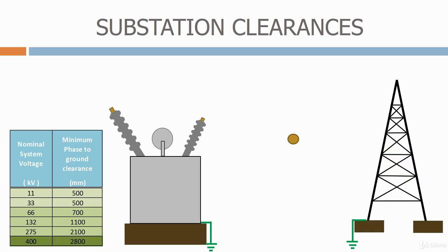Here we have an energized bare conductor in a substation. All we need to do is draw a circle around the live conductor. The radius of the circle is the minimum phase-to-ground clearance distance, and no grounded equipment can be allowed to enter the circle. At 11 kV, the radius of the circle will be 500 mm. As the voltage increases, the radius of the circle increases. At 275 kV, the radius will be 2.1 meters.